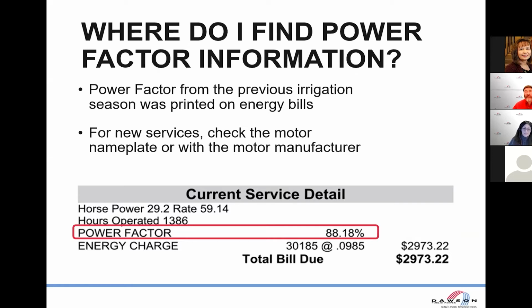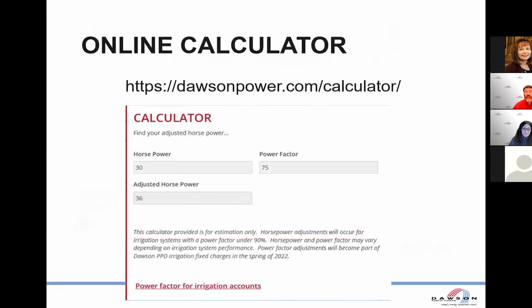Now, power factor fluctuates with the loads on the motor. So you'll want to make sure that we measure that at peak, right? If you're going to measure it yourself, and that your manufacturer gets that for you. Now, if you want to see how it's going to affect your horsepower on your bill, we have a handy tool we put on our website. So you can go to dawsonpower.com/calculator and use that to find your adjusted horsepower.